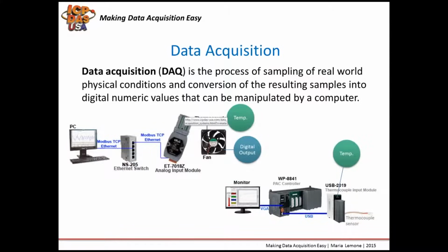Data acquisition, abbreviated DAQ, is the process of sampling real-world physical information and the conversion of the sampled data into digital numeric values that can be understood by computers and controllers. This picture here shows a data acquisition computer program with trending, graphing program running on a PC connected to an Ethernet switch, which is connected to an Ethernet-based thermocouple input and digital output module. The program takes the temperature data and triggers a fan to turn on or off through the digital output on the ET7018Z module based on the temperature determined by the thermocouple sensor.